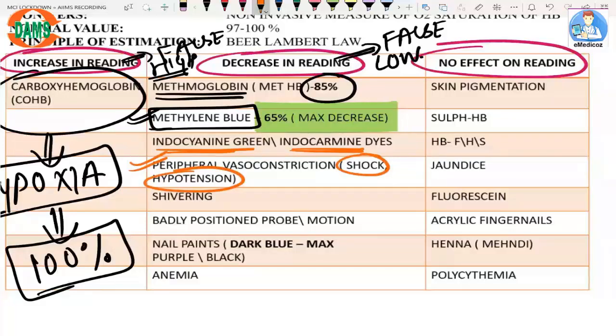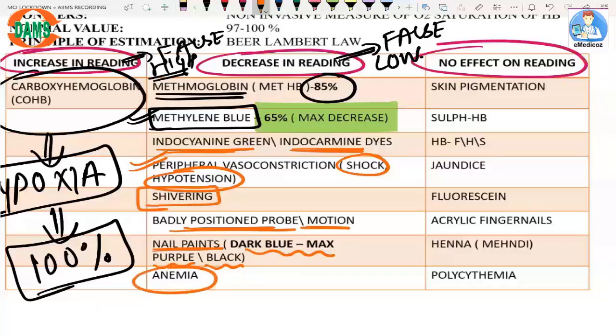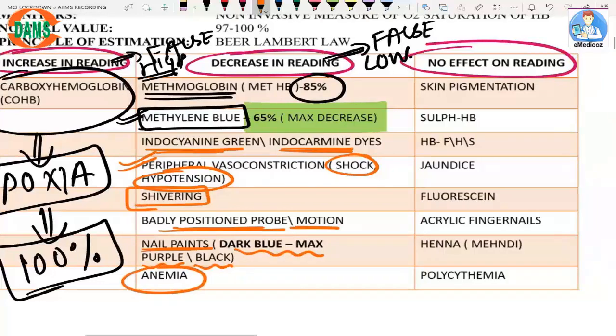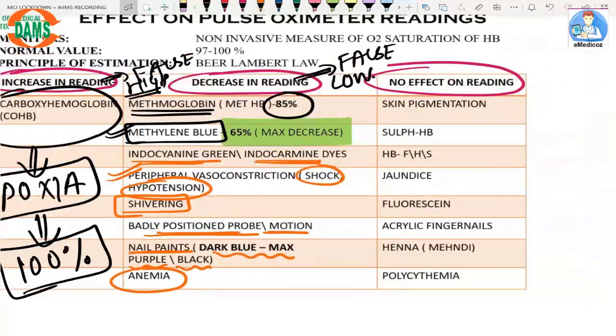Additional causes of falsely low readings include shivering, a badly positioned probe, motion artifact, and dark nail paints — maximum effect from dark blue, purple, or black colors — and anemia. All these conditions decrease the reading on the pulse oximeter.